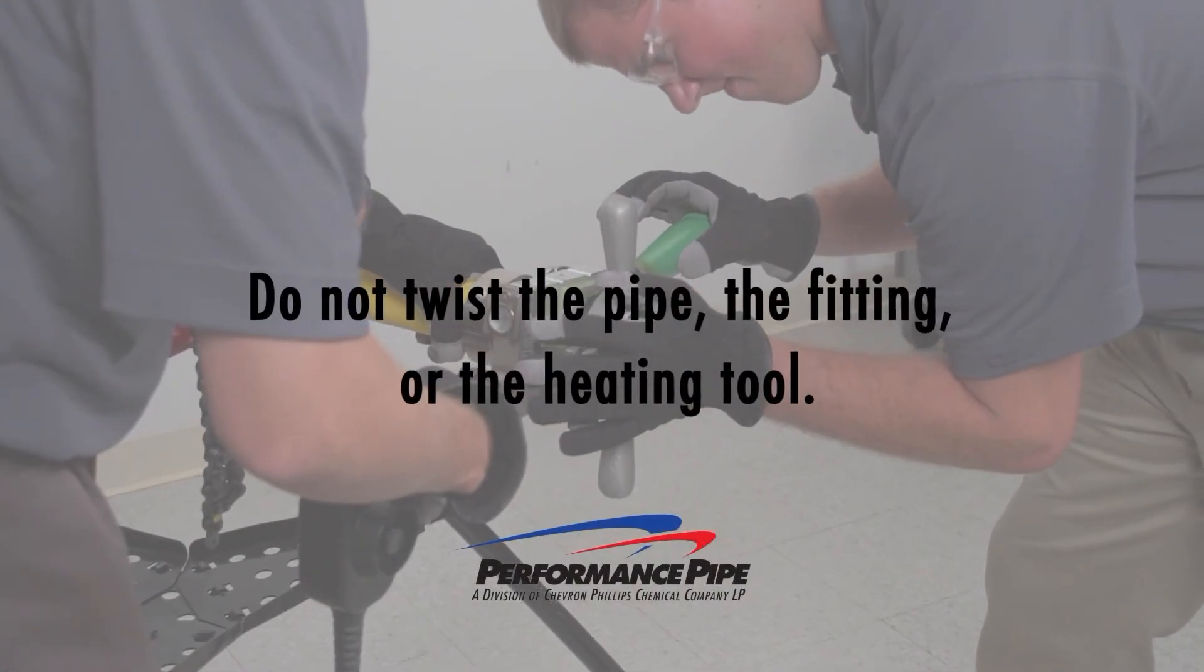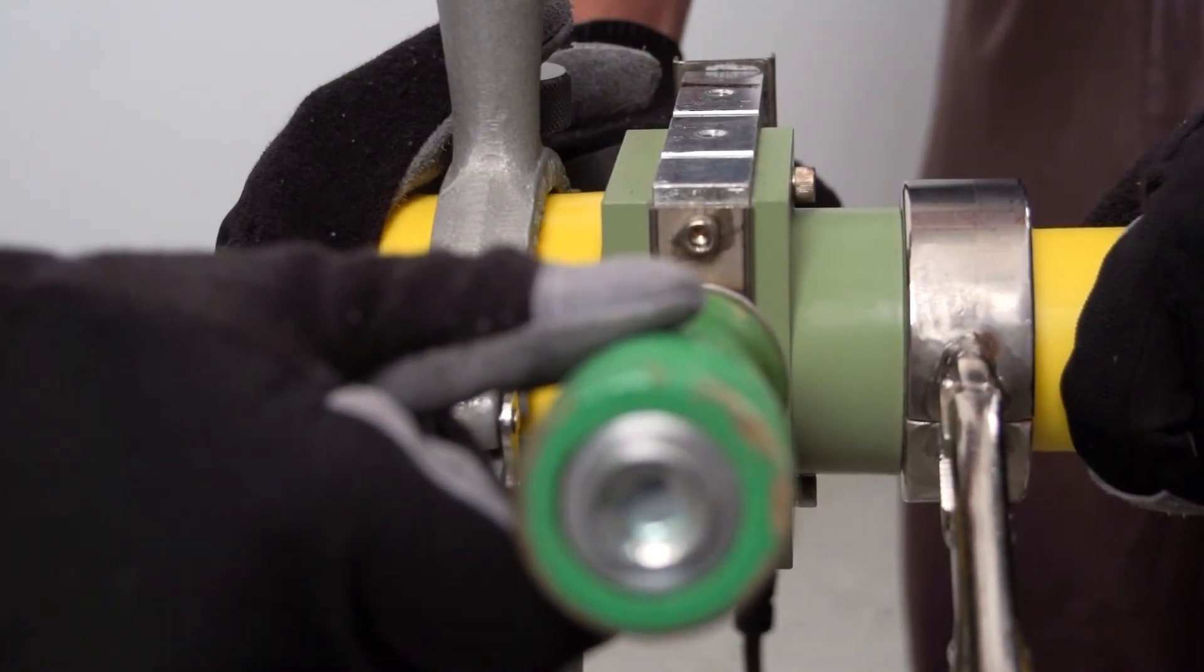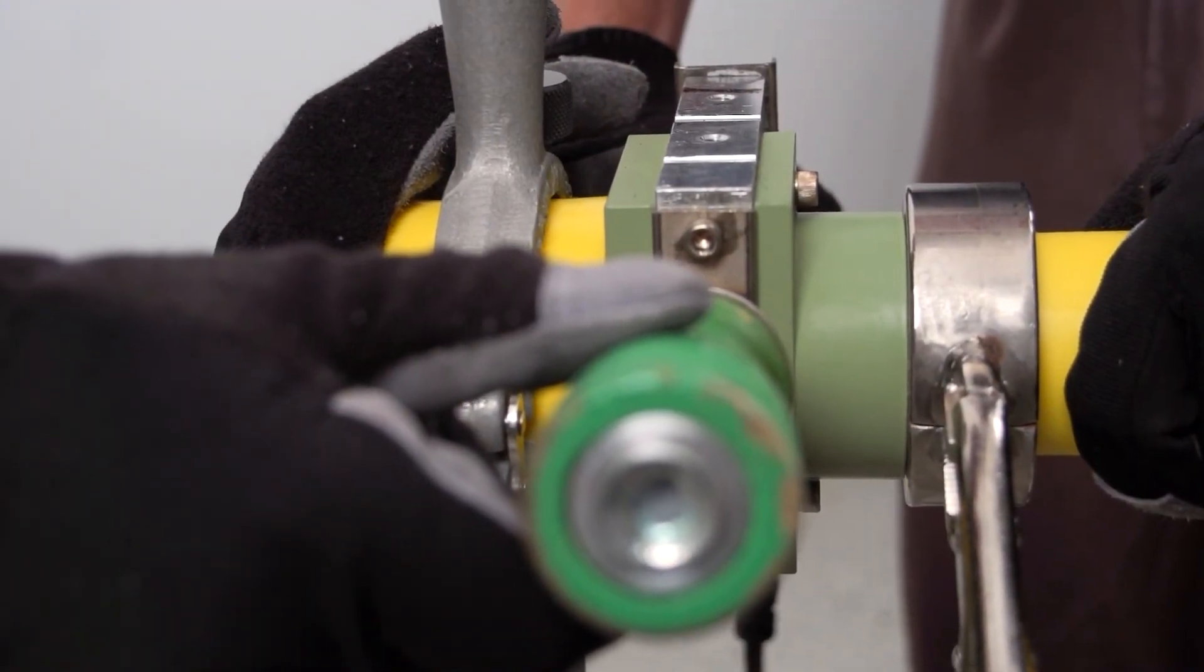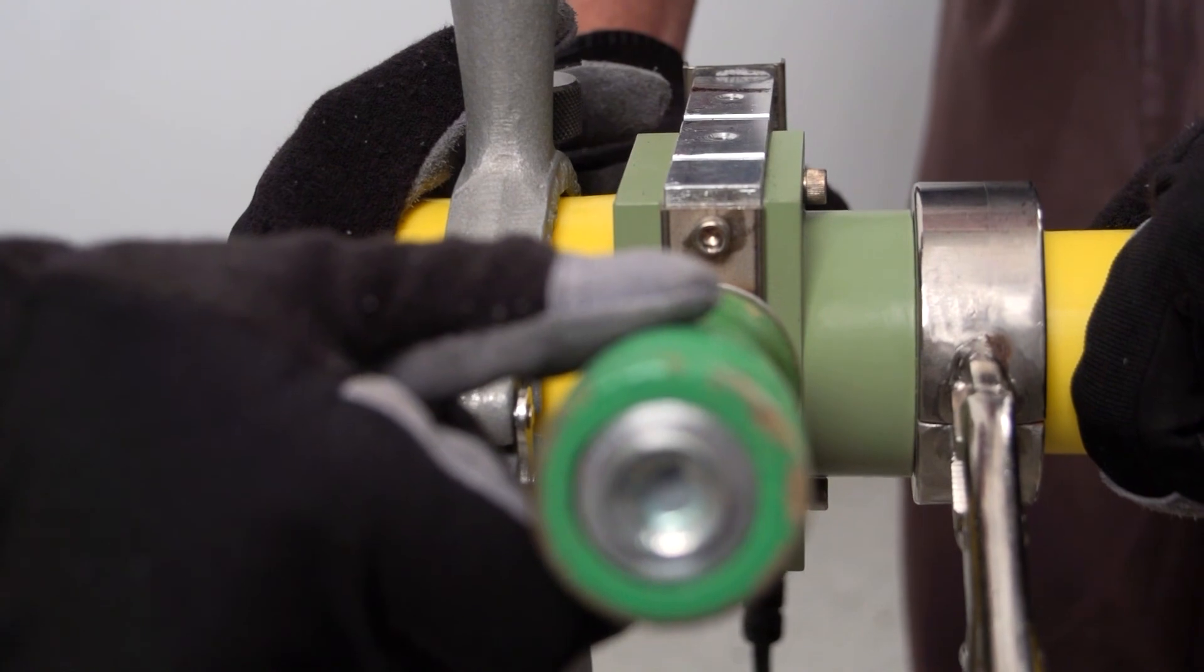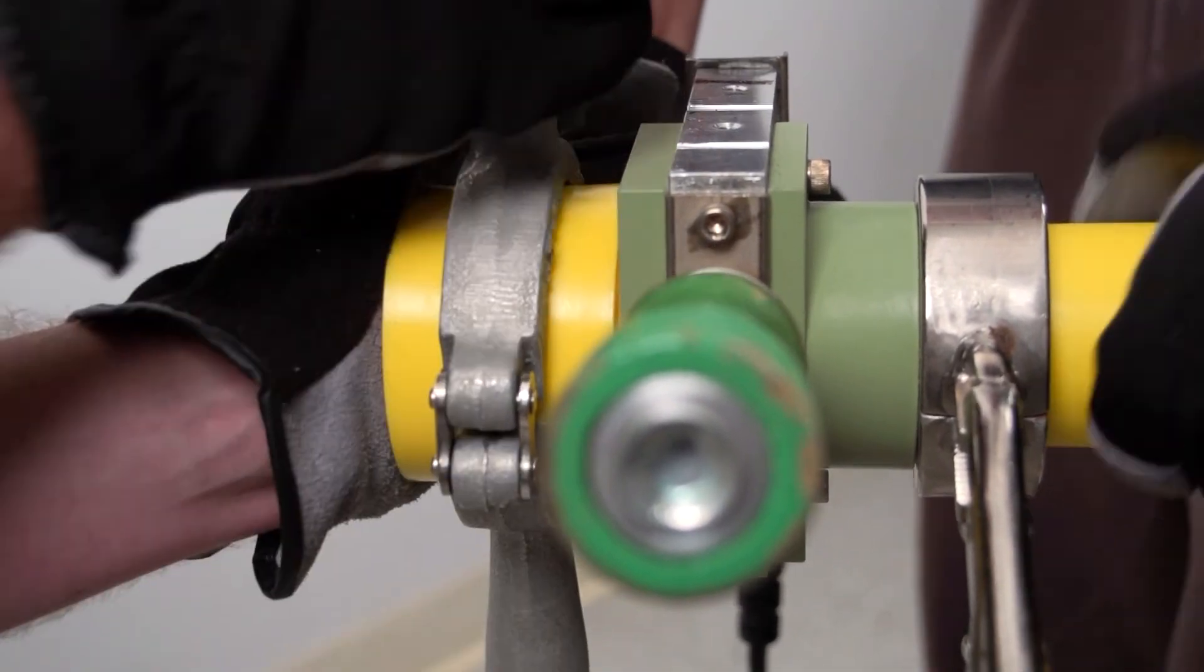Do not twist the pipe, the fitting, or the heating tool. At the end of the heating time, quickly and simultaneously remove the pipe and fitting from the heating tool using a snap action. Remove the pipe and fitting straight out from the heating tool faces. Do not twist or displace the melt. If the pipe or fitting are removed at an angle or twisted, melt can be displaced and the joint may leak or fail.